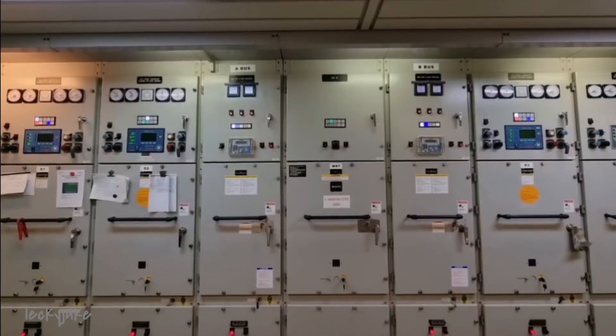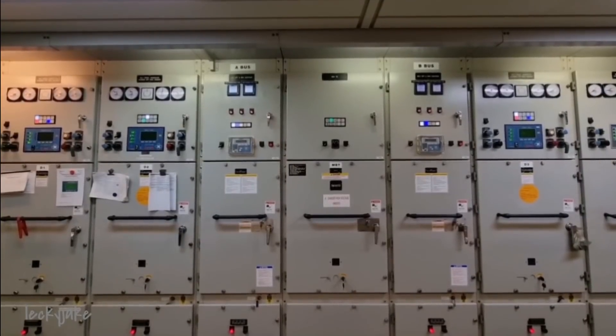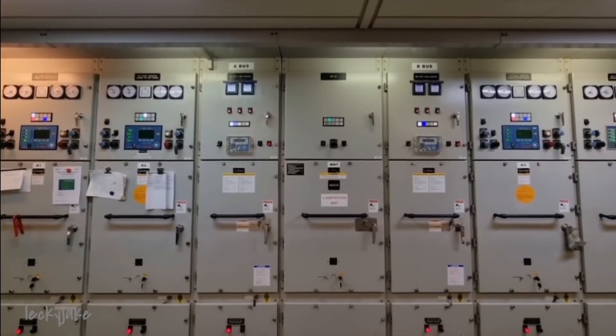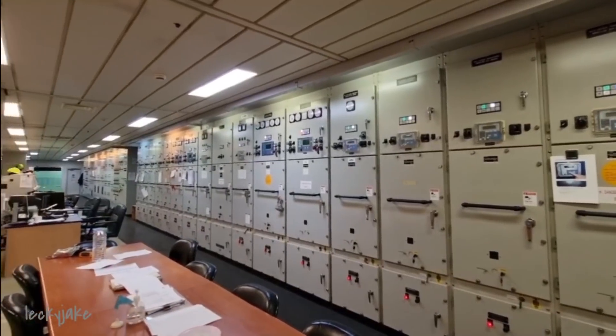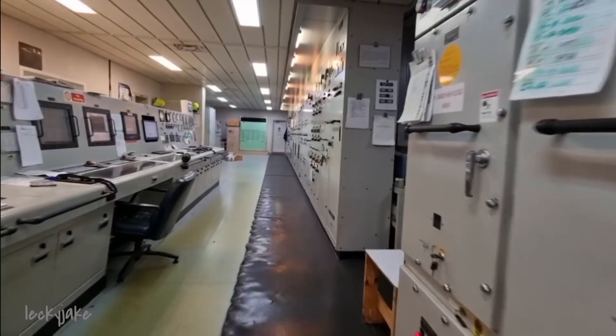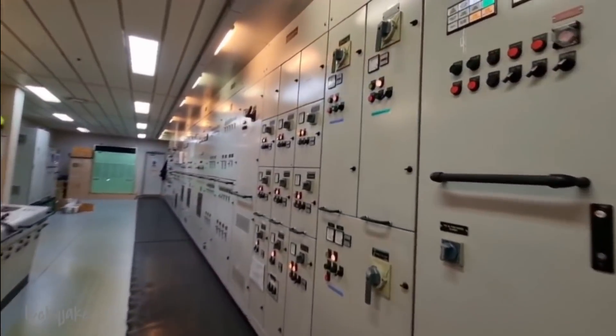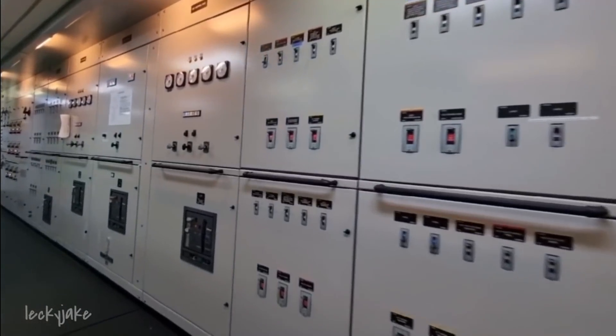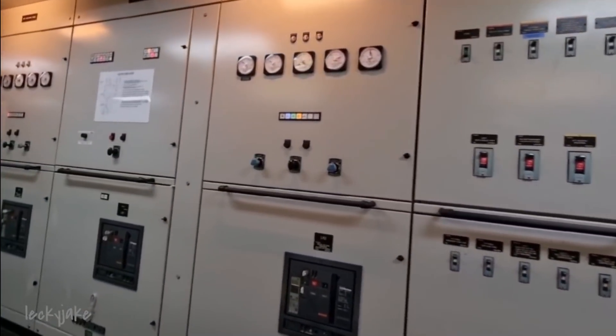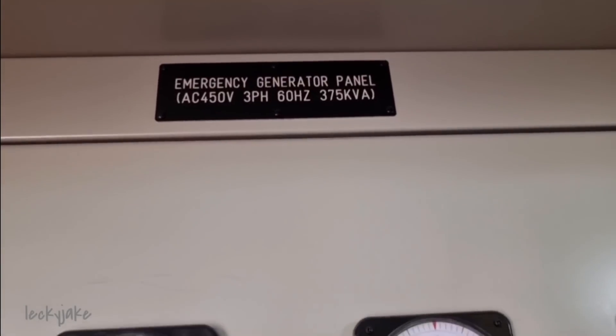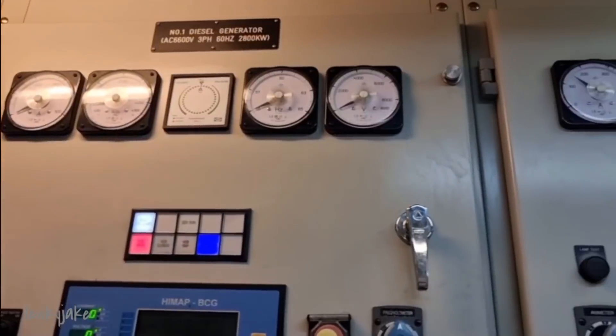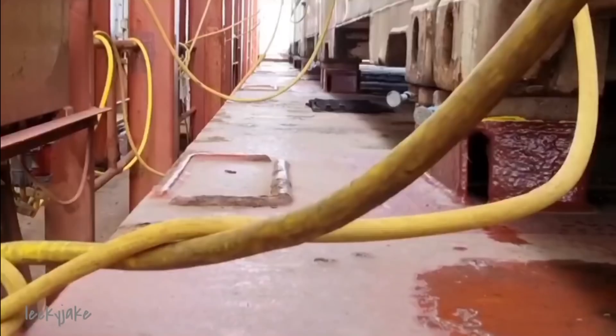The generators supply 6600 volts at 60 hertz to the main switchboard which is situated in the engine control room. The number of generators connected to the main switchboard at one time depends on the electrical consumer load of the ship at that time. The generators can be manually run up and connected to the main switchboard as required. But in normal operation, the automatic control system automatically controls the operation of the generators and major operational aspects of the main switchboard.